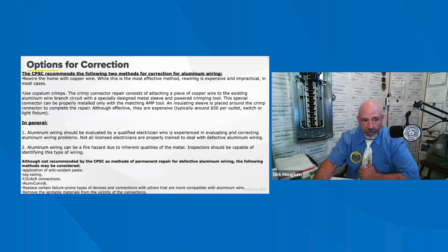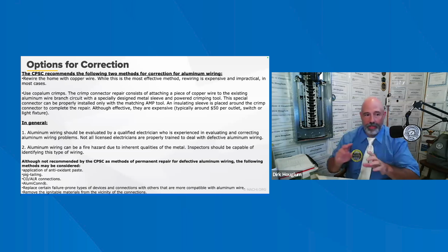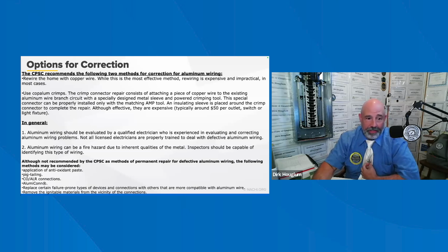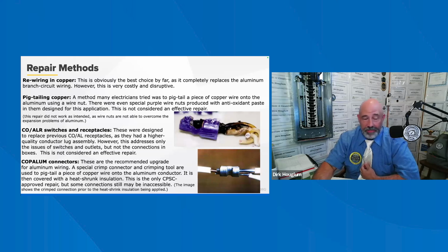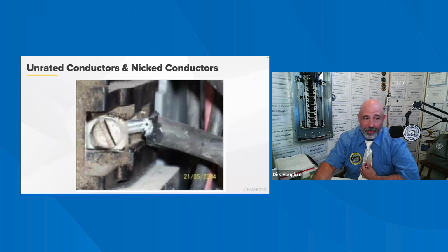Let's see, options for correction. A lot of the time you want to see the crimps there, the copalum crimps. I can't really say that word. Those are when they can tie the copper and aluminum together so that it can be a little bit more safe. This is what happens when you wire copper and aluminum together too. It can burn out, so we don't want to see that happening. The only time that it's acceptable is in small amounts.